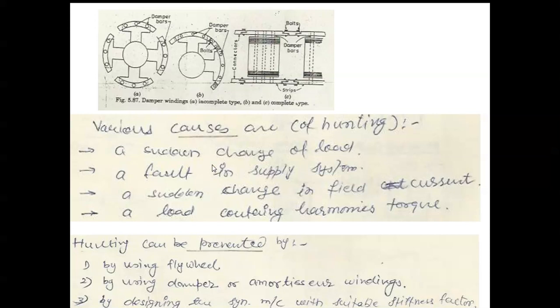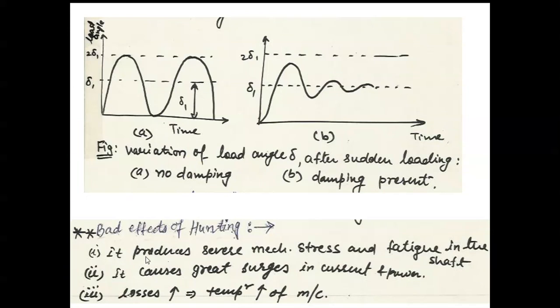Because of hunting, there are certain bad effects on the machine. It produces severe mechanical stress on the rotor and there may be fatigue in the shaft — alternating clockwise and anticlockwise stress may cause shaft failure. Second, oscillations produce large surges in current and power — sudden rises or falls in voltage, current, or power — increasing losses and raising the machine's temperature.